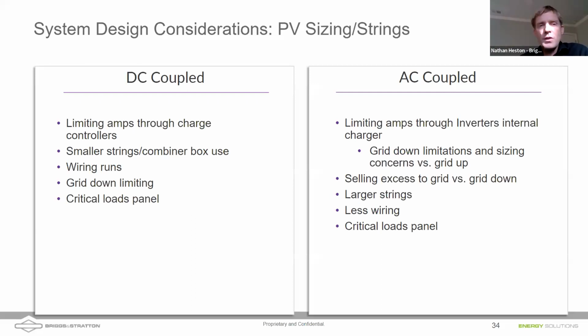It's also important to consider your wiring runs and make sure you're using cabling of equal length. And then there are limitations for grid down as well. If you have equipment like our inverter, you'll want to put a critical loads panel in there, so you're not trying to pull 200 amps out of an inverter that's only capable of 40, right? So you'll want to pay attention to this and add a critical loads panel.